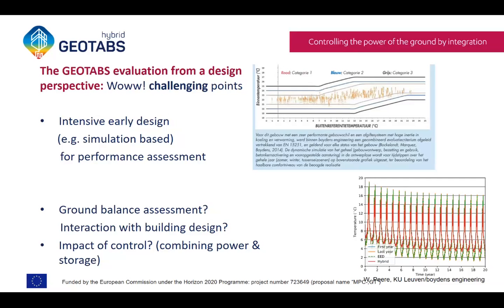That means, as you probably know from the design or sizing question of domestic hot water systems, you have the liberty of increasing or downsizing the storage and giving a bit more power on the supply side, the heat pump. So we have a lot of possibilities, and the issue is: what will I do, what is cost optimal? But also, how is it controlled in the end? If you use a lot of storage but the loading control isn't done properly, you could have a problem. So how you control the system in operation can impact how you should size it.